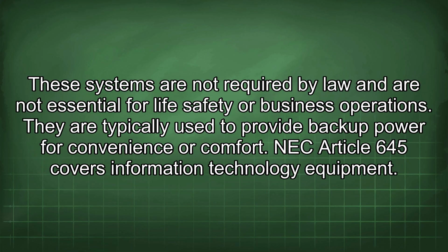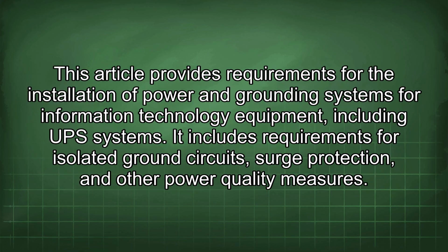These systems are not required by law and are not essential for life safety or business operations. They are typically used to provide backup power for convenience or comfort. NEC Article 645 covers information technology equipment. This article provides requirements for the installation of power and grounding systems for information technology equipment, including UPS systems. It includes requirements for isolated ground circuits, surge protection, and other power quality measures.